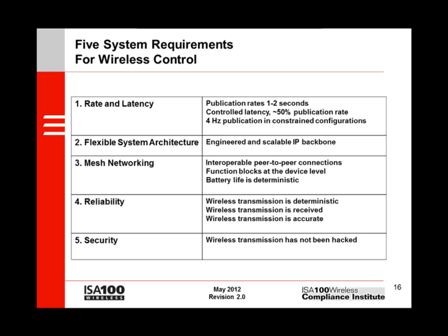The ISA-100 standard was designed to support reporting rates of four times per second, or possibly more, in meticulously engineered installations. Second, if your network can't be architected for the performance you need, the rest of this list doesn't matter. The designers of ISA-100 believe that whenever control is involved, the network needs to be carefully engineered as an extension of a mature and scalable IP backbone. This bias is clear in the standard, and it's also clear in ISA-100 products. Third, true mesh networking is a practical requirement for controls. For time-critical control applications, it might not be acceptable to wait for a message to travel all the way to a controller and then all the way back again wirelessly. For those network configurations, control needs to involve a simple and direct wireless connection between devices. These connections need to keep running even if the mesh network operation is temporarily interrupted.